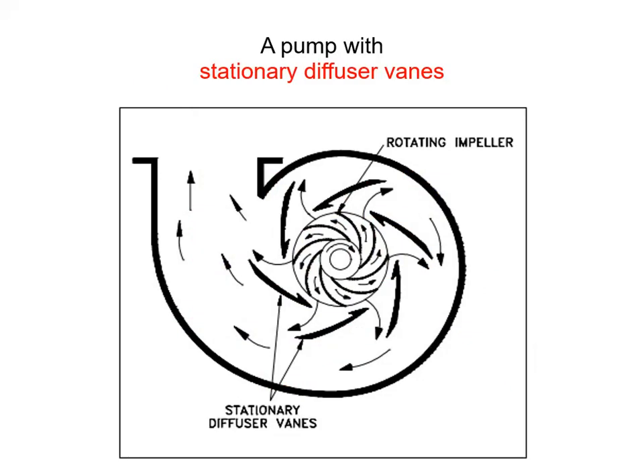In certain centrifugal pumps, typically the larger ones, there can be stationary diffuser vanes. Fluid that comes out of the rotating impeller blades goes in between these fixed diffuser vanes. The aim is to have a more controlled expansion of the flow area, a more controlled decrease in velocity, and therefore a more controlled increase of pressure, resulting in a more efficient pump.